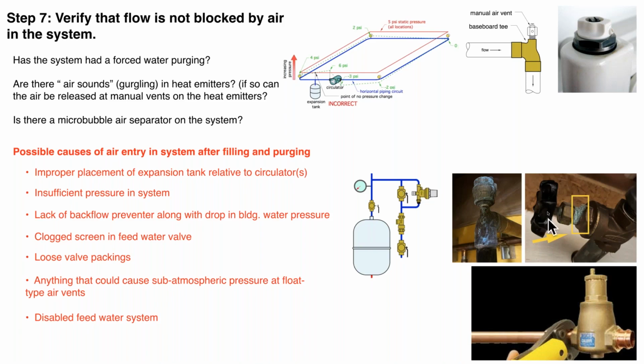Here's an example over here where you can see this crusty film, or flakes, on the outside of a valve. That tells me that bonnet is leaking. Here's another one of a float type air vent where obviously there's been water leaking out of this thing. Or a disabled feed water system. If somebody has shut off that feed water valve, over time that pressure inevitably will go down, and you could get to a condition where air is drawn back into the system or something is causing a blockage of flow.